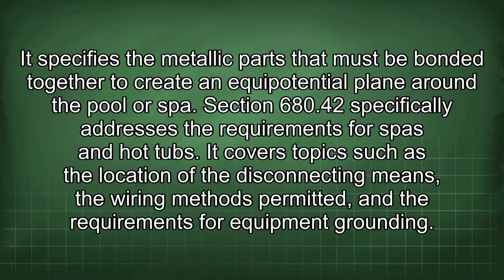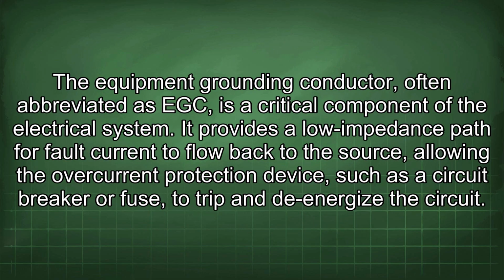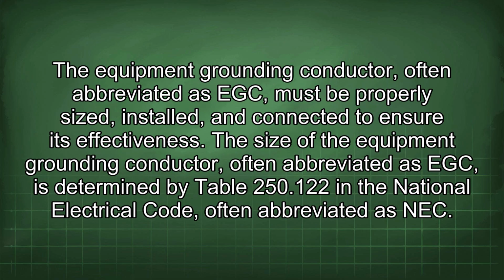Section 680.42 specifically addresses the requirements for spas and hot tubs. It covers topics such as the location of the disconnecting means, the wiring methods permitted, and the requirements for equipment grounding. The equipment grounding conductor, often abbreviated as EGC, is a critical component of the electrical system. It provides a low impedance path for fault current to flow back to the source, allowing the overcurrent protection device, such as a circuit breaker or fuse, to trip and de-energize the circuit. The EGC must be properly sized, installed, and connected to ensure its effectiveness.